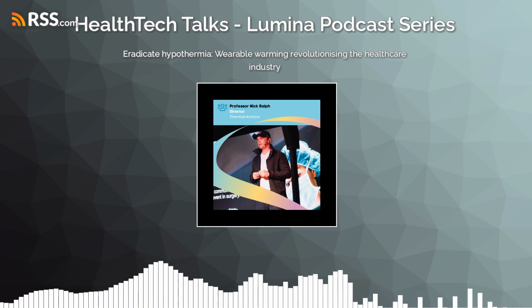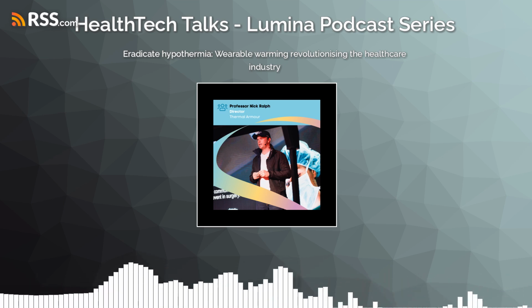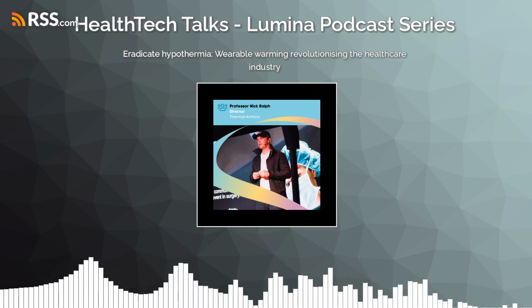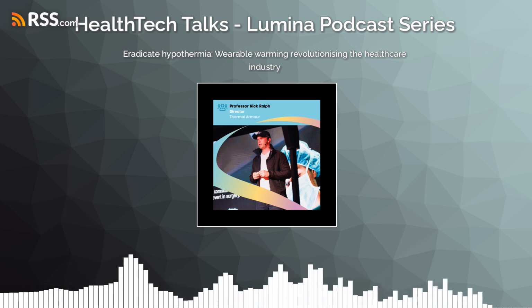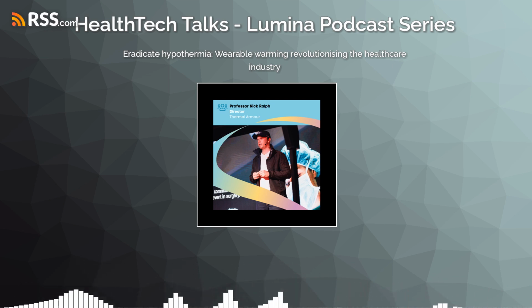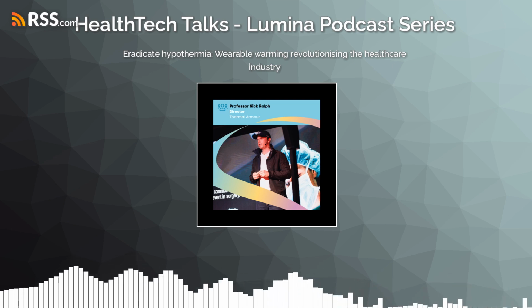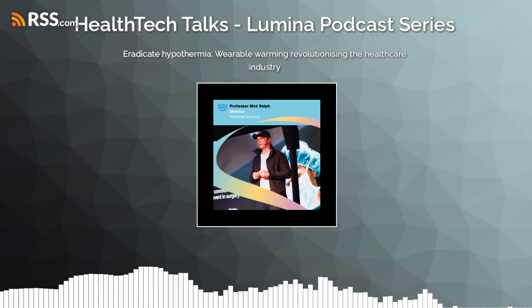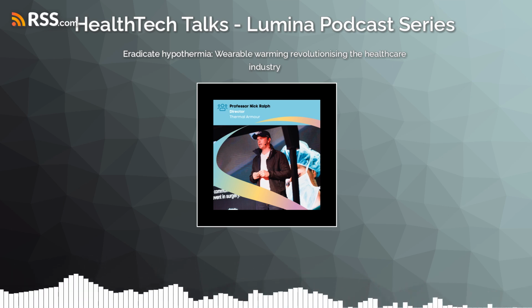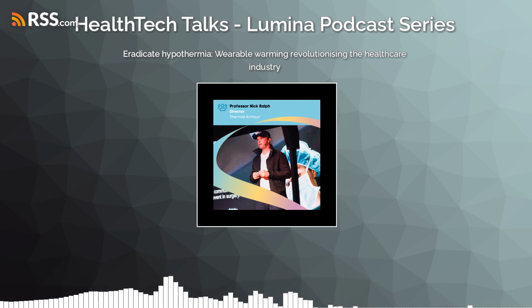So can you explain the product, how it works and how it improves patient outcomes? Yeah, so basically we have a conductive heat layer, which is based off a polymer. That polymer, through our patented design processes, which I can't talk about too much, heats up to a very, very rapid level. So we've got the fastest heating product on the market. It heats up in under 2 minutes. We can actually get it to heat up in about 30 seconds, but it's a compromise between battery life and whether you're on wall power or not. What we did notice was that when we were working on this polymer and heating it up, it was very uniform, very fast to heat and very well insulated.